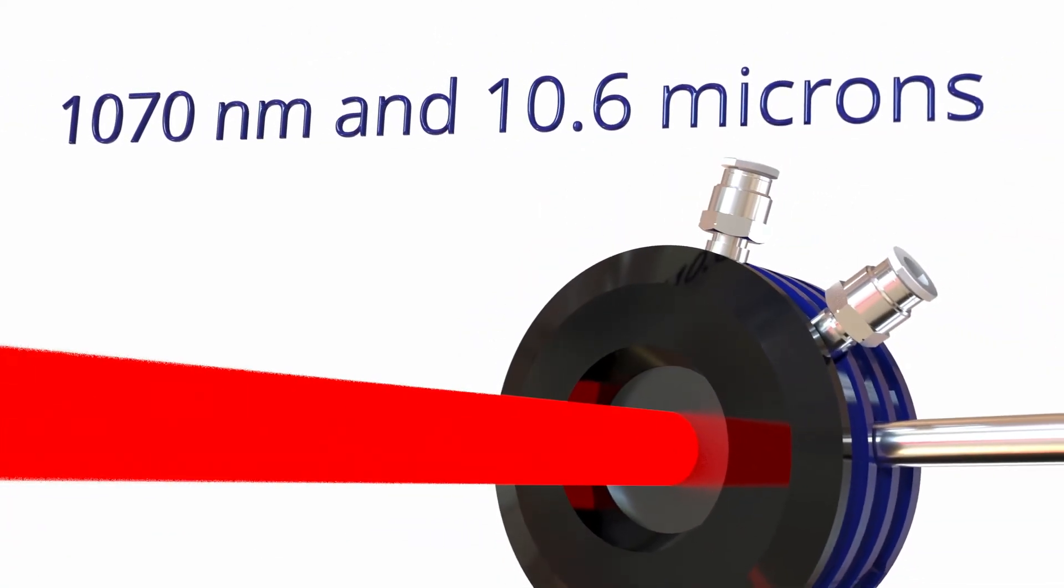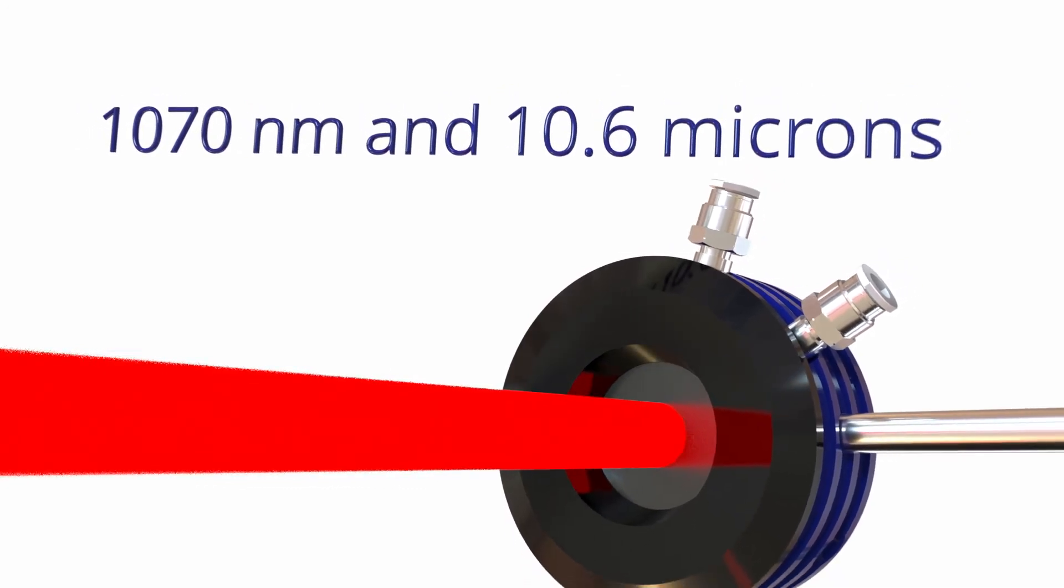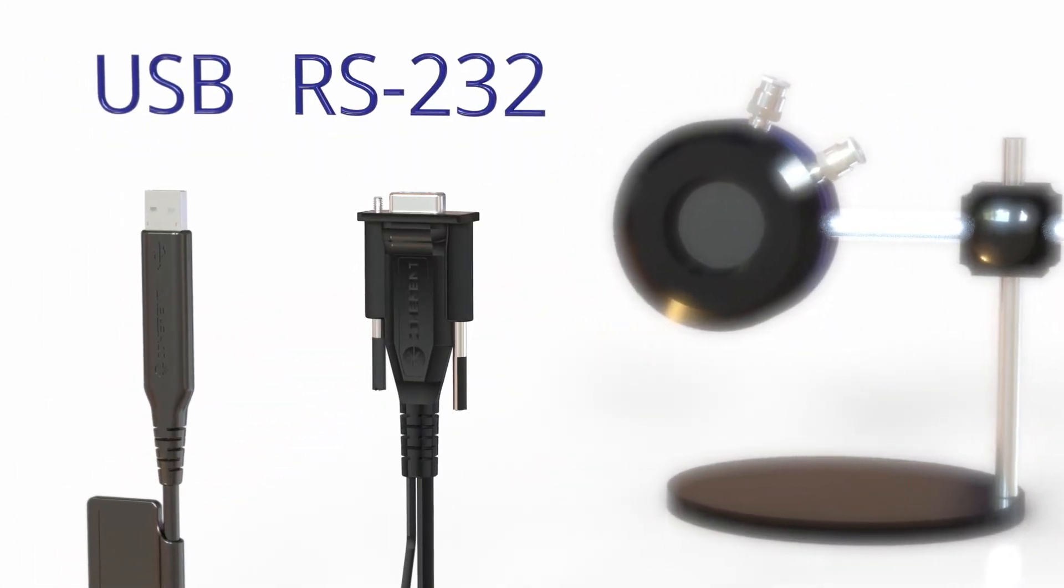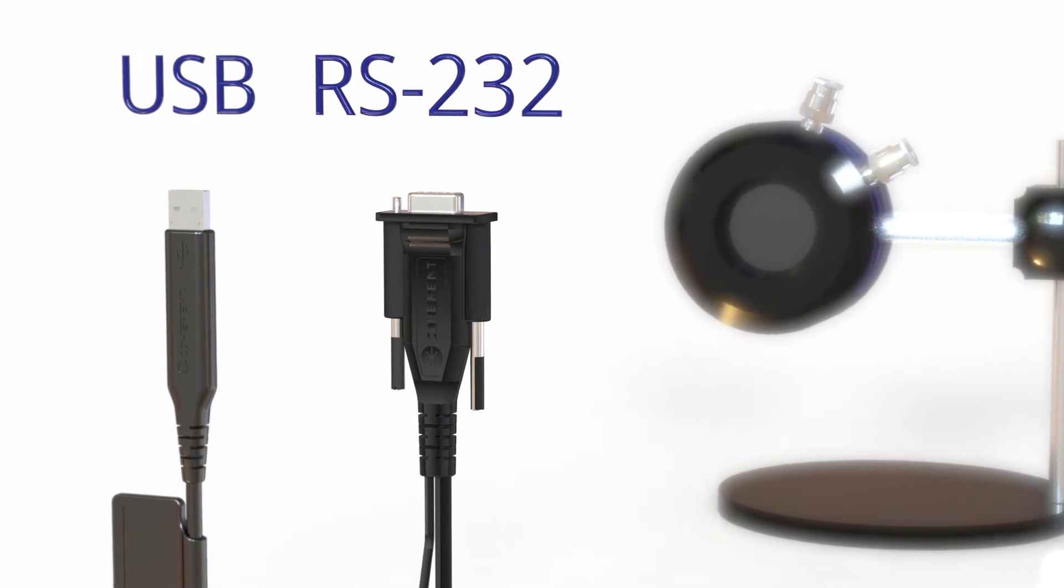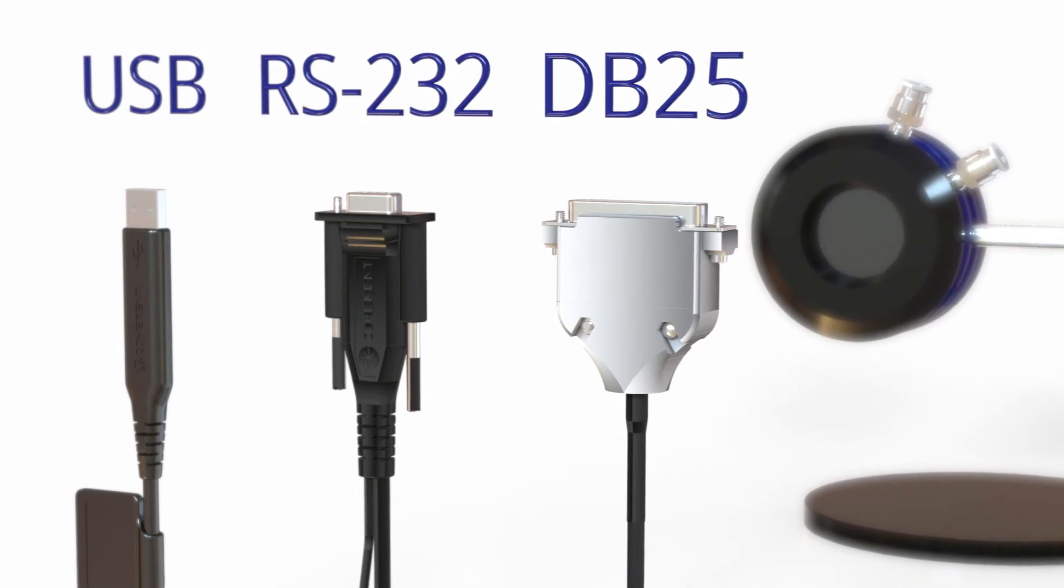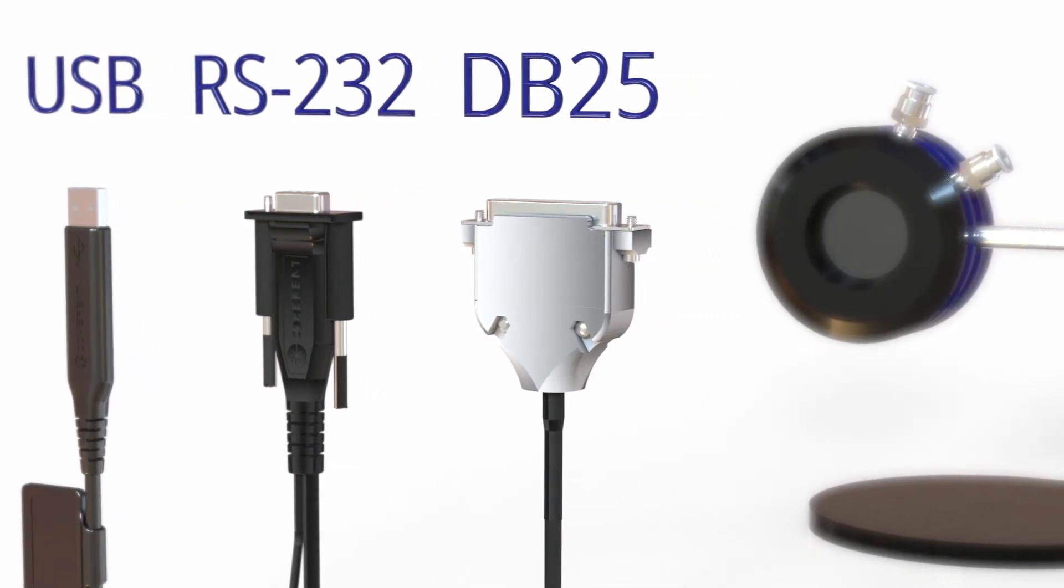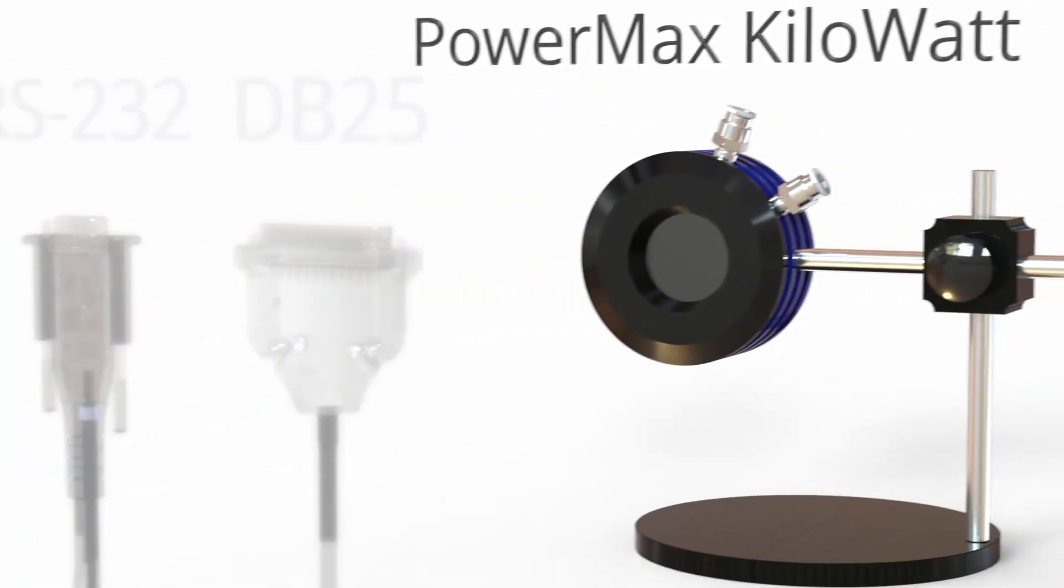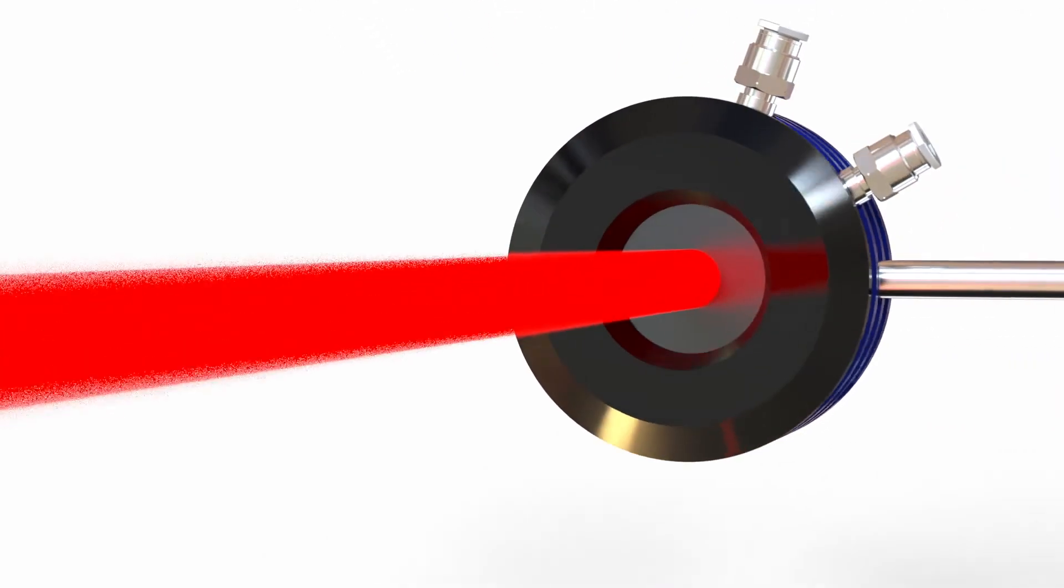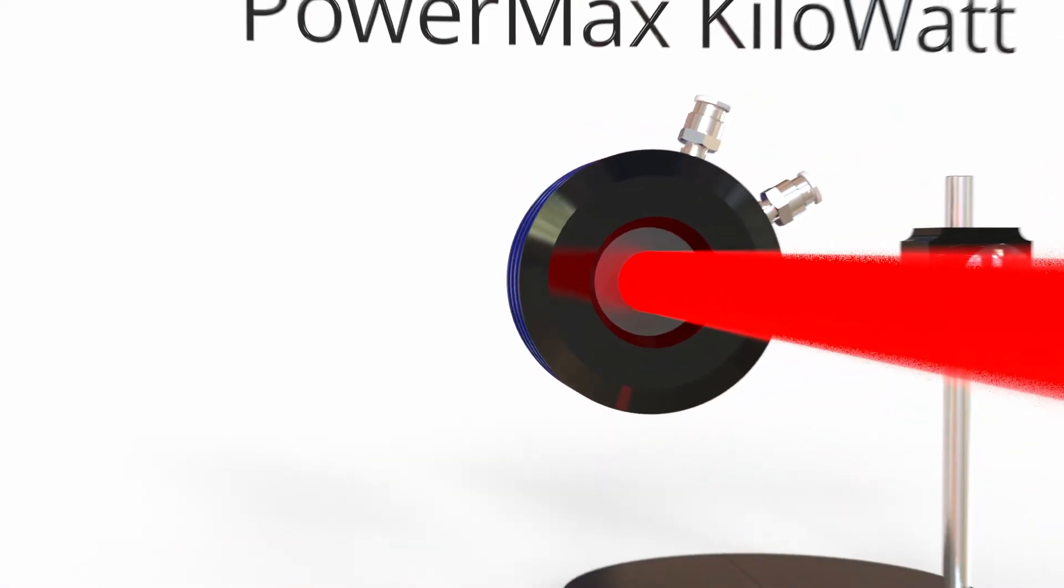All models are calibrated at two wavelengths and at two power levels. Choose from USB and RS-232 configurations for direct connection to a PC or industrial controller and DB25 for use with our standalone meters. PowerMax kilowatt sensors. High power sensors for high power applications. From Coherent.